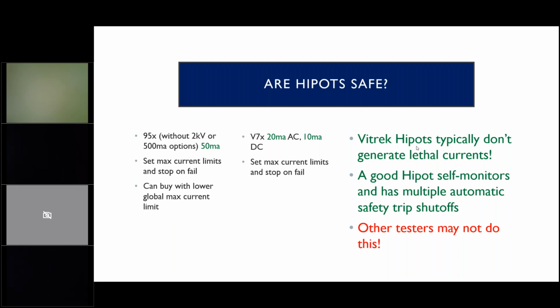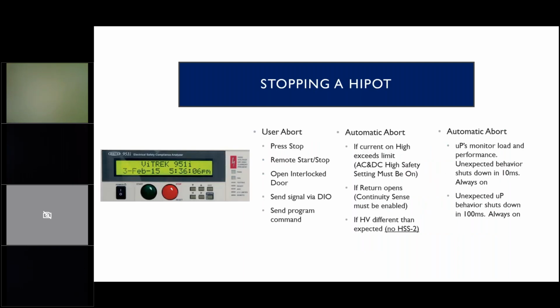So, our HIPOTs generally don't put out lethal currents. Also, a good HIPOT self-monitors and has multiple automatic safety trip shutoffs. Other testers may not do this, especially the old testers. In the old days, a HIPOT was basically just a step-up transformer. It was connected to the wall, and it would put out a lot of current. And they didn't have a lot of safety. As a matter of fact, probably no safety measures were put on those things. Sometimes I walk around factories and I'll see this big old HIPOT from days past, and they can be quite a bit more dangerous.